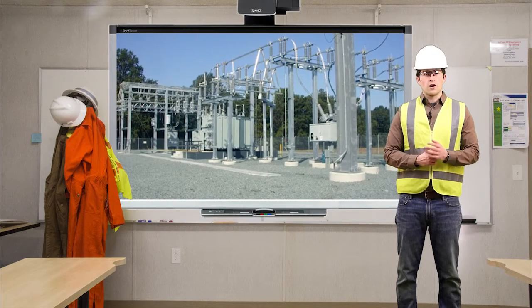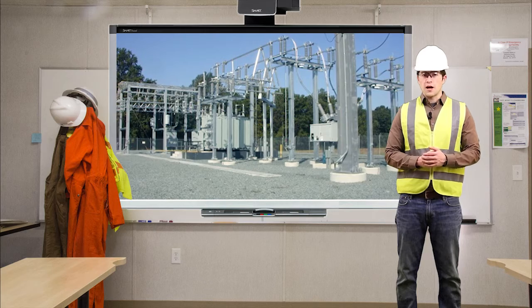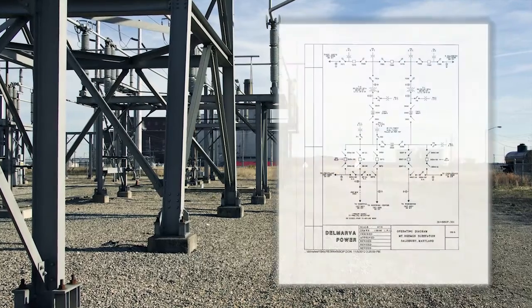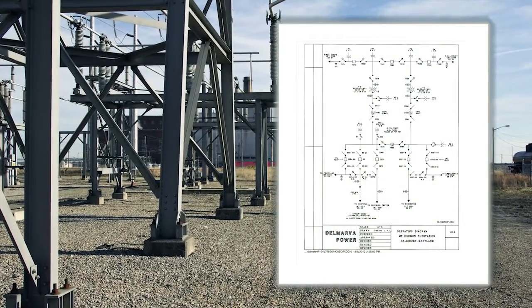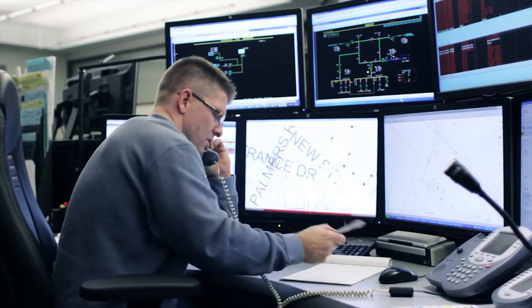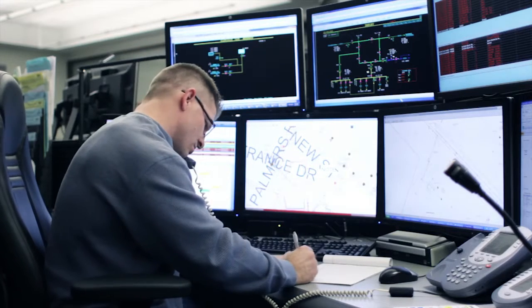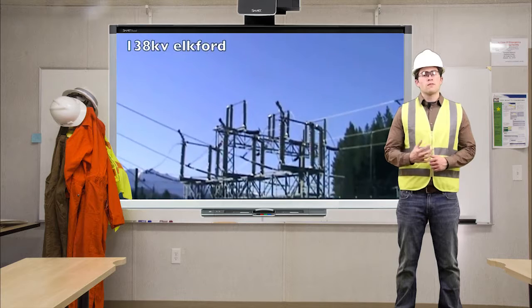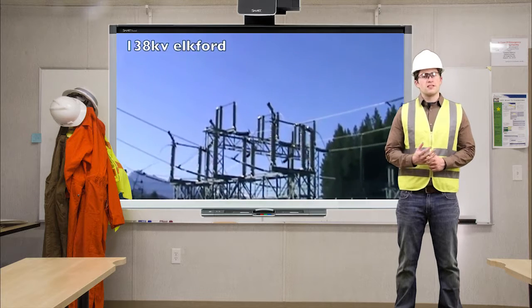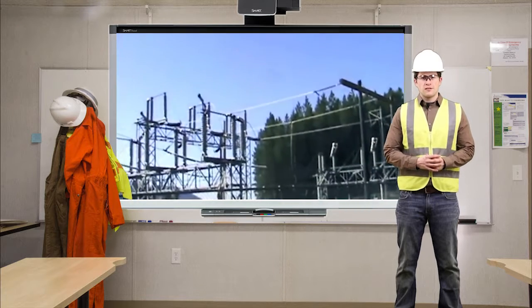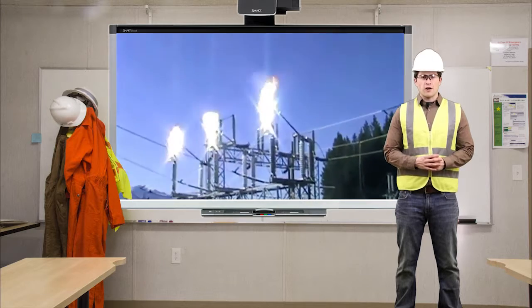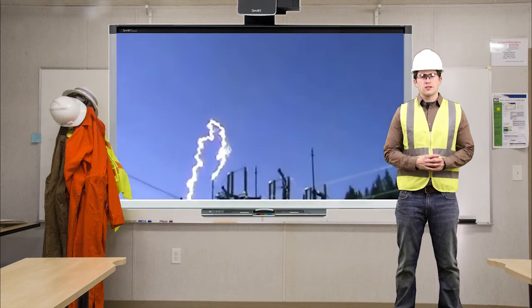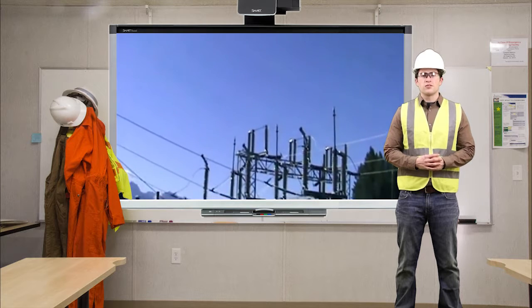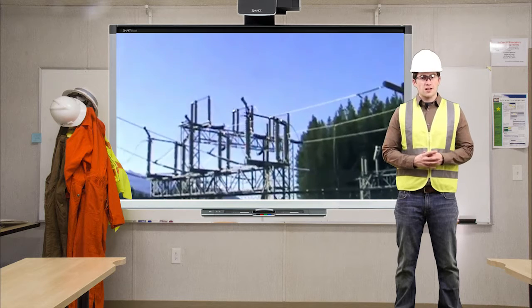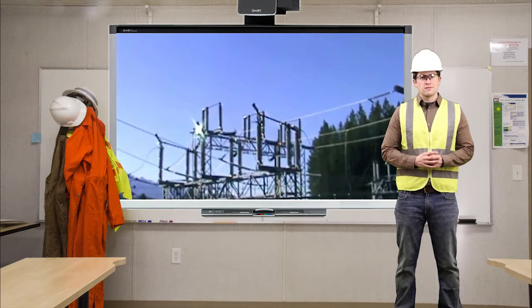As stated earlier, a qualified worker must be able to determine the nominal voltage of exposed live parts. This is accomplished on-site using the substation operating diagram provided by your liaison or information from a system operator to obtain the nominal voltage of equipment. One of the most obvious hazards in a substation is the danger associated with electricity. Electricity is not visible outside of an arc. Therefore, always treat conductors and associated equipment as energized until the conductors and equipment are de-energized, tested, and grounded.